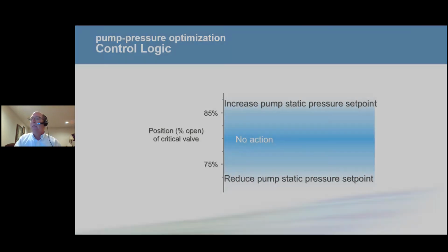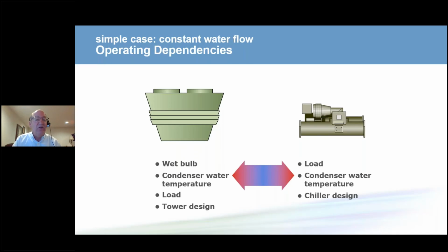The last thing we'll talk about is chiller tower optimization. Many people want to reduce the tower water temperature to reduce the chiller power, because what connects the chiller and the cooling tower is the water temperature. The tower will produce the water temperature based on the wet bulb, the heat rejection load, and its design. The chiller's power will change depending on its design and its load, but the one that connects these two is the leaving tower temperature, which is the entering condenser water temperature. And the question is, how do we control that?